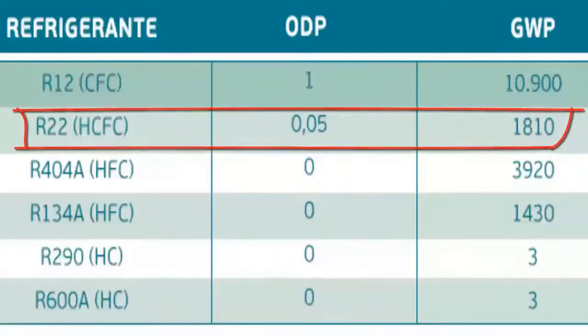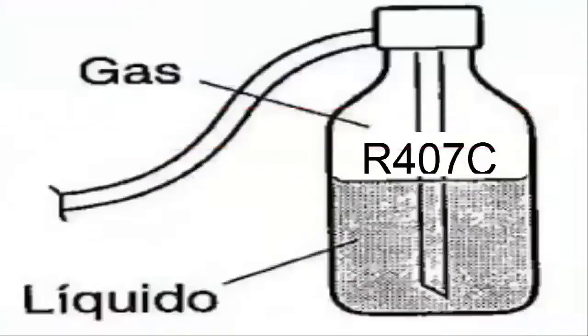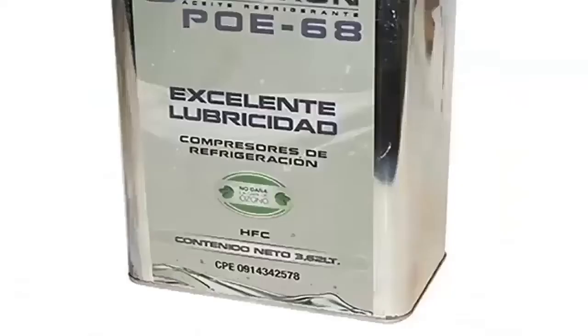The charge with R407C must be carried out in liquid phase, and POE-type oil must also be used. For this reason, an oil change is often required if the compressor previously used mineral oil.